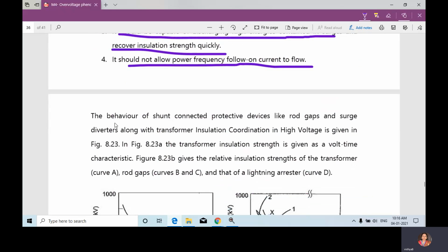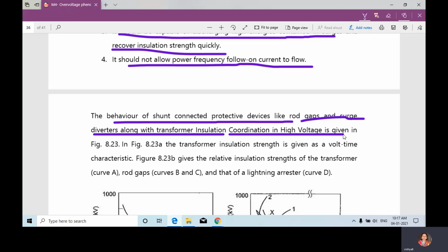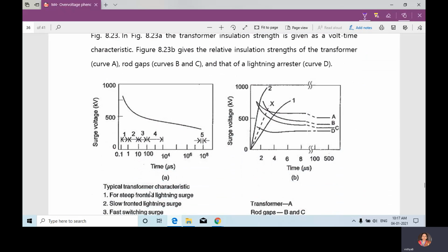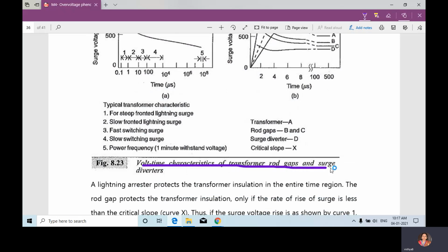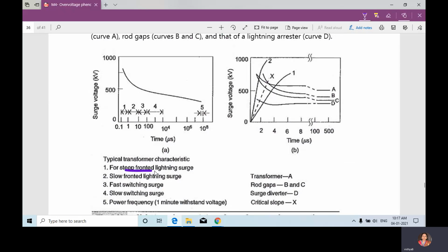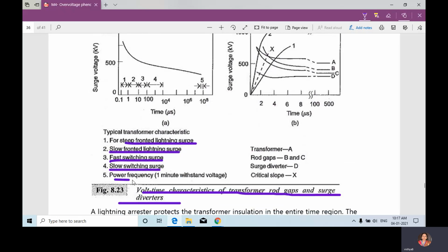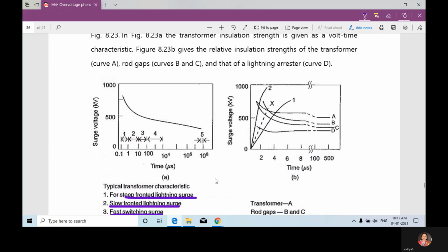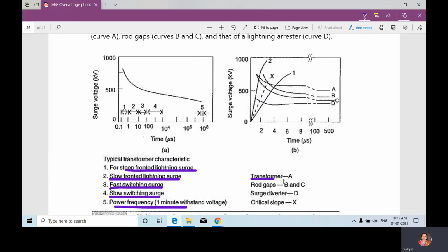Okay. Next, the behavior of shunt connected protective devices, like rod gaps and surge diverters, along with the transformer insulation coordination in high voltage is given by this figure. Volt-time characteristics of a transformer, rod gaps, and surge diverters. One is a steep fronted lightning surge, two is a slow fronted lightning surge, three is a fast switching surge, four is a slow switching surge, five is the power frequency one minute withstand voltage. And in figure B, A is the transformer, B and C are the rod gaps, and D is a surge diverter. X is the critical slope.